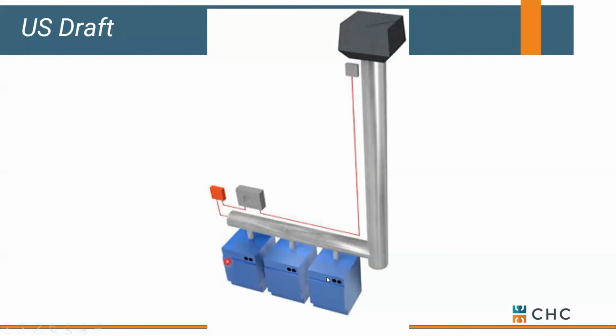You can certainly have multiple boilers tied into a common stack in a mechanical draft system on the roof. But dealing with US Draft, they're like, hey, if you've got a choice to vent without a mechanical draft system, that's the way to go. But if you're struggling getting vent runs out of your mechanical room, more than happy to sell you a system. Just be careful, this can get a little pricey on you. Typically $8,000 to $15,000 is a good budget for a mechanical draft system. So that's one thing to consider when you're replacing boilers. More than likely, you're going to have to upgrade your vent system as well.